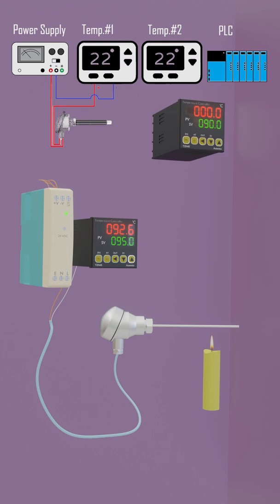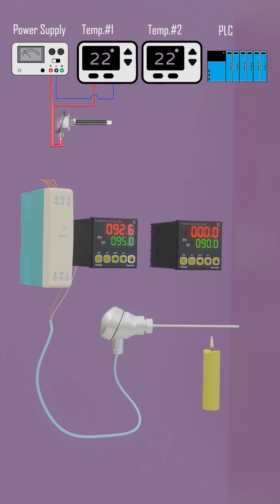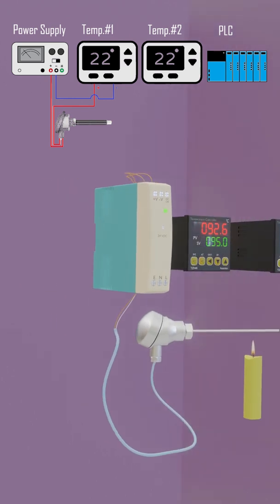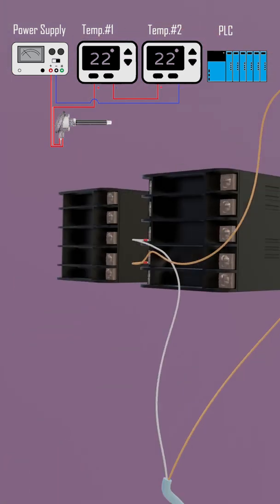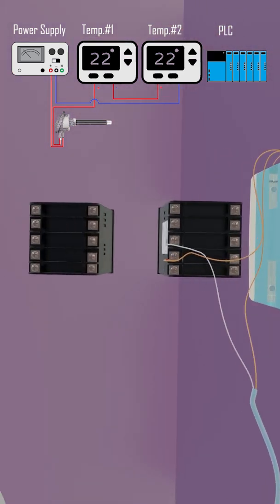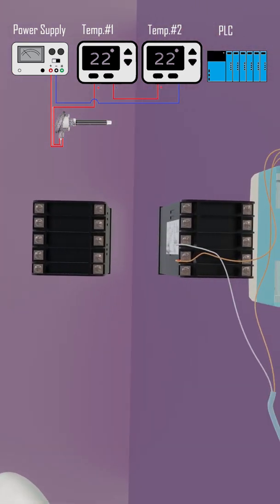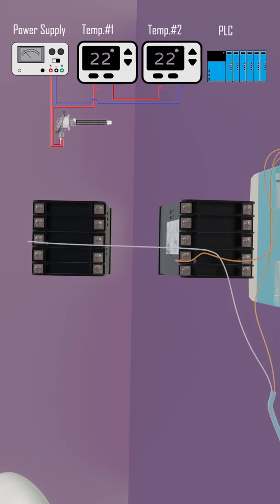Let's suppose if we want to show the readings of the same temperature sensor on another temperature indicator, we have simply put this temperature indicator in series with the circuit. We simply remove the negative analog signal wire from the controller and fix this wire at the positive signal input of the other controller.